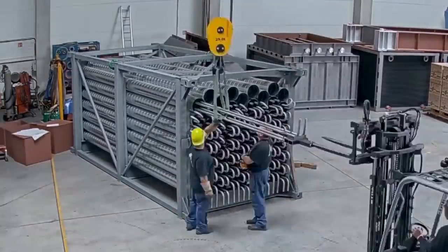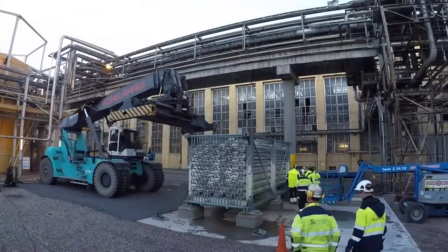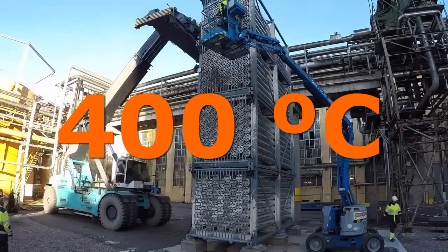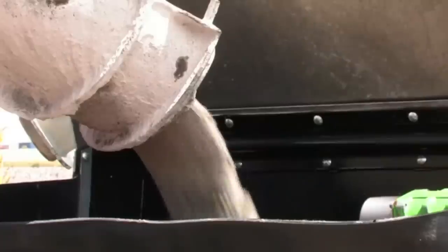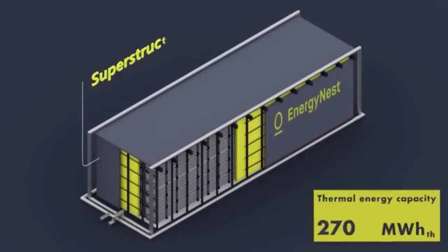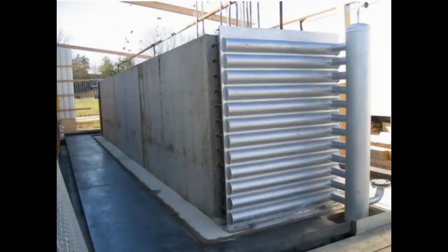This heat storage consists of a large number of long cylinders of concrete round pipes. If hot thermal oil circulates through those pipes, it transfers its thermal energy to the concrete. As a result, the concrete is heated to high temperatures, up to 400°C. We can also extract this thermal energy from the concrete through the circulation of thermal oil through the same pipes. This was an example from EnergyNest, which started building concrete heat storages a few years ago and recently received a big investment. This is a German heat storage from a large mass of concrete with a large number of pipes for the circulation of thermal oil.